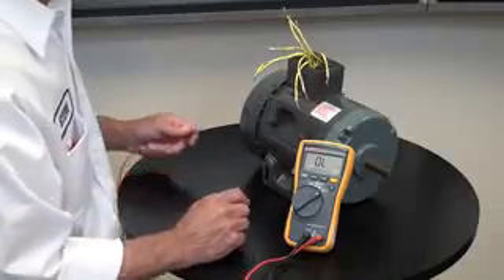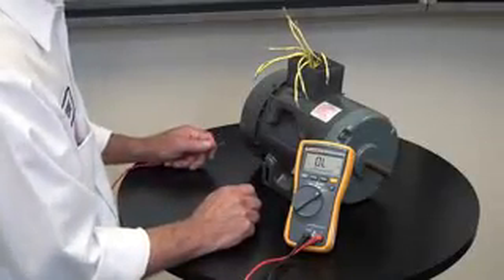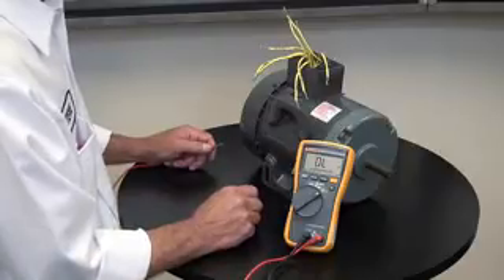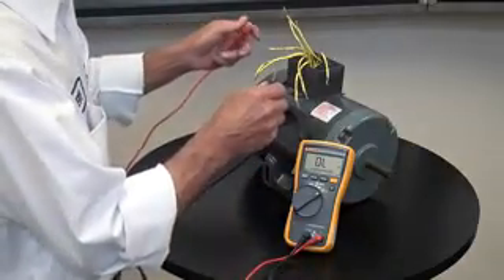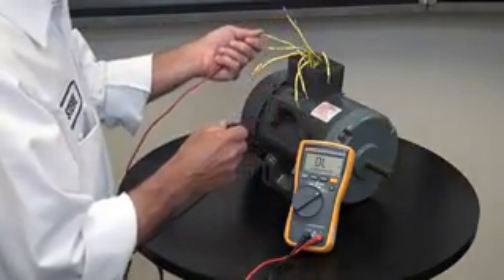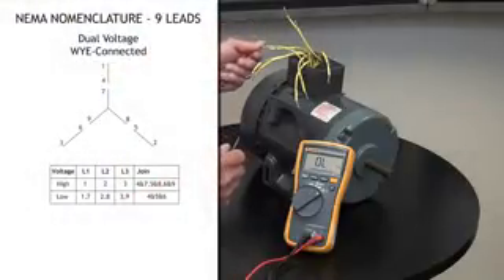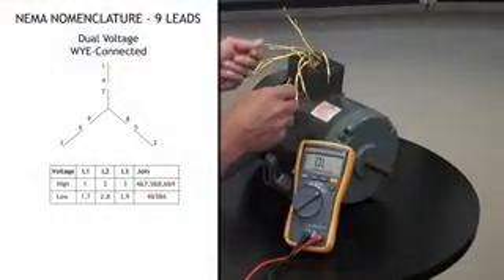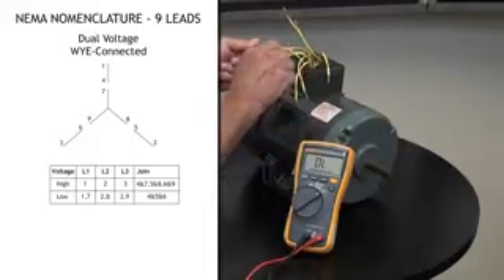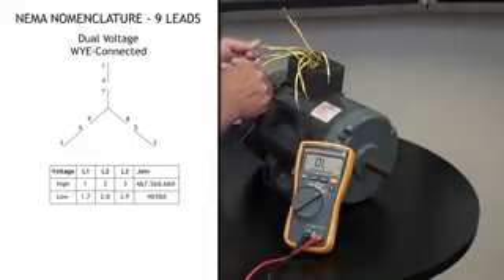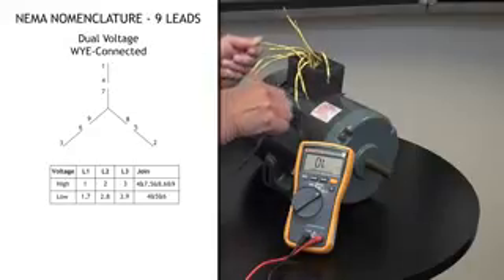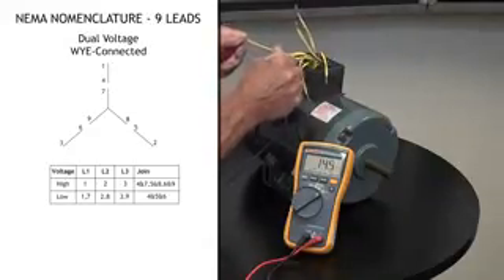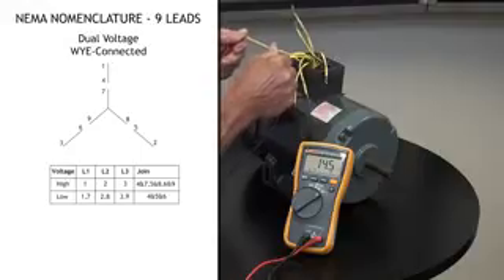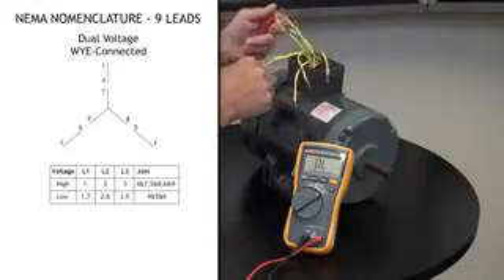First thing we need to do is to determine whether we've got either a Y or a delta internal connection to the motor. So what we're going to do is take a number that's already identified. Let's say we've got number 2, and we're going to check to see what has continuity with the number 2. We've got one lead that has continuity with number 2. And then we're going to continue on.